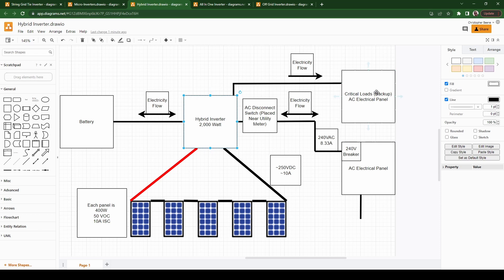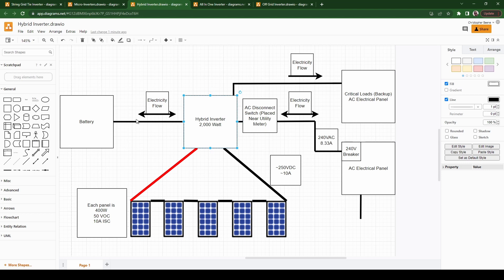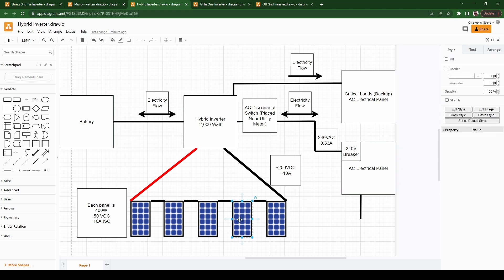The way that the hybrid inverter works is you have a separate output that will go to this critical loads panel. In normal day-to-day operation you're either pulling power from the grid at night when there's no solar, or you're pulling power from the solar panels to feed the critical loads. If you ever do lose the grid or the AC disconnect switch is off, then you still have panels and battery to feed the critical loads. In a grid down scenario you can still run some stuff. Obviously the battery can be charged and discharged. You can actually charge the battery from the grid or from the panels. Hybrid inverter very flexible but usually two to three times the cost of a grid tie string inverter.